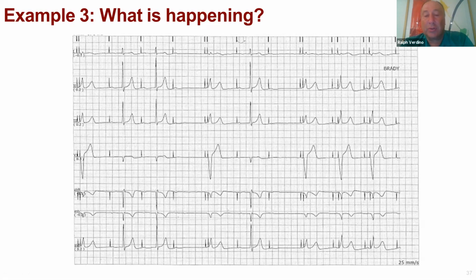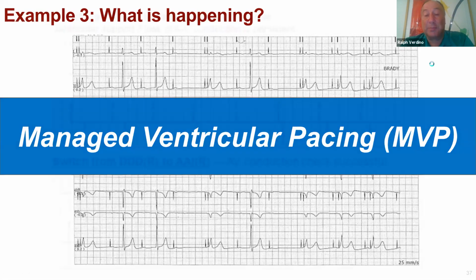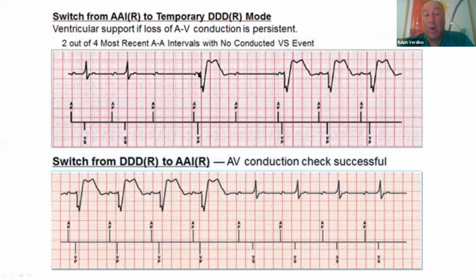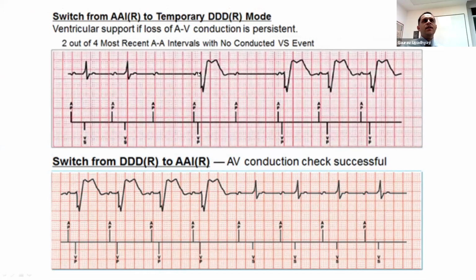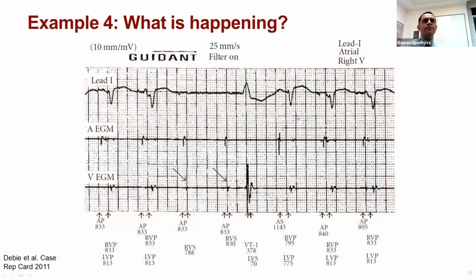Not only that it allows you to drop a beat, but it lets you know that it did let you drop the beat, and it's giving the next beat as a paced complex with a sub-physiologic AV delay. And here's an example of that here, that sub-physiologic AV delay. Great. The first return has it when it switches modes. Exactly.